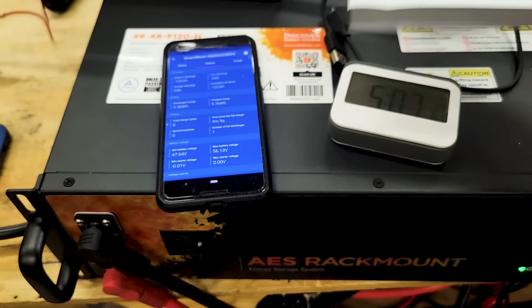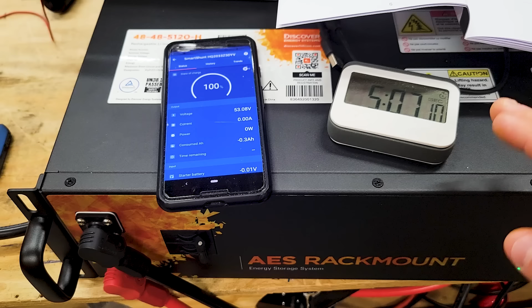What's cool is the BMS inside here, the battery management system, it uses relays instead of MOSFETs. And those are 200 amp relays. So we shouldn't break anything. If this thing doesn't turn back on, if we let out the magic smoke, we know that something's wrong. But hopefully it can handle this 200 amp test without a problem.